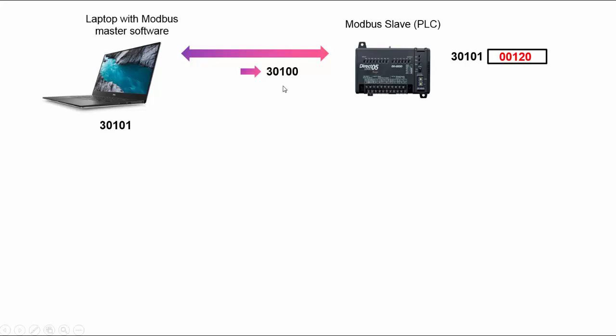No, I didn't make a mistake. It will actually send the address which is one less than what you typed in. This believe it or not is in the Modbus protocol specification and it's horrible. I don't know why they did this.